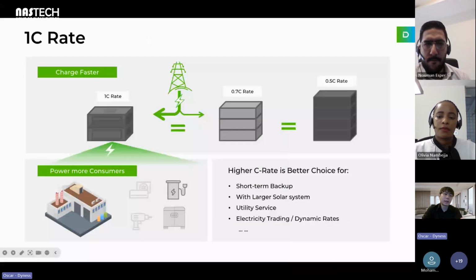Until now, we can see that in the market, most high voltage C&I batteries apply a 0.5 or maybe 0.7 C rate. Our Stack100 supports a 1C rate, which means if you are using a 100 kilowatt PCS, you only need 100 kilowatt-hour batteries to reach the same level of charging and discharging power. That means you are saving almost half the cost to reach the same project solution. If you are using a 0.5C rate battery with a 100 kilowatt PCS, you would have to apply 200 kilowatt-hour batteries, which is twice the price.